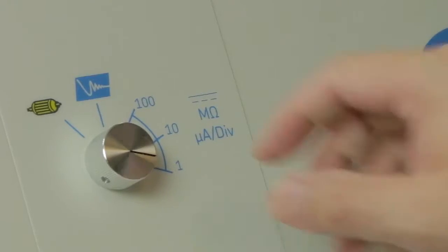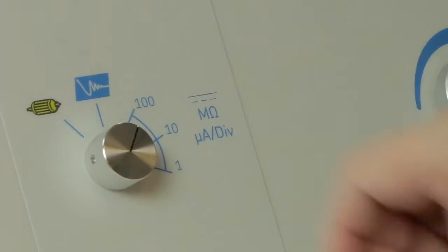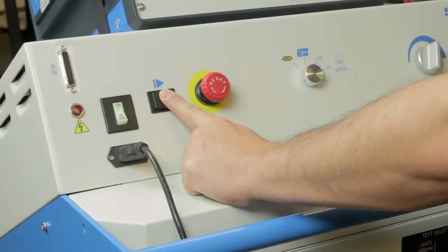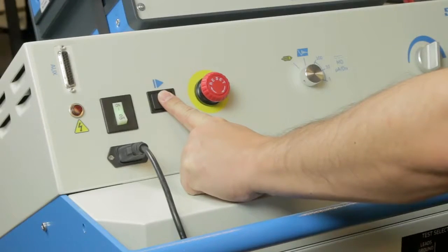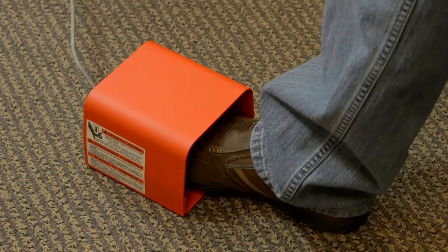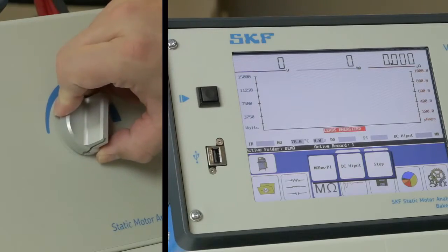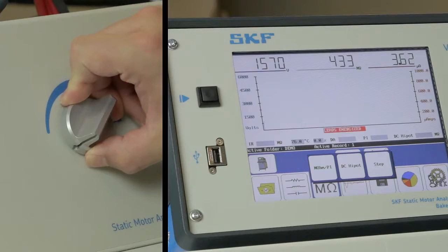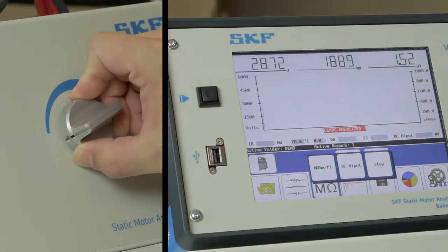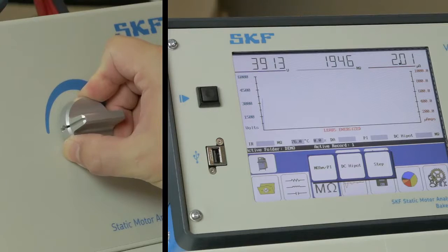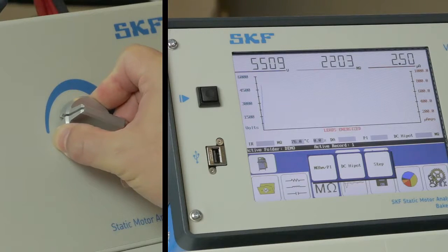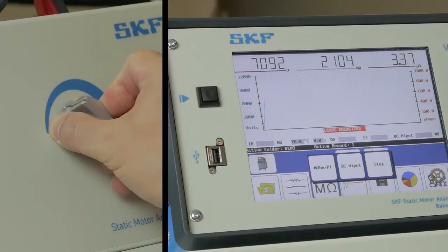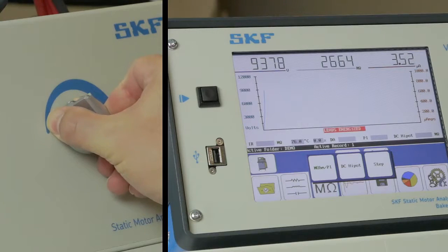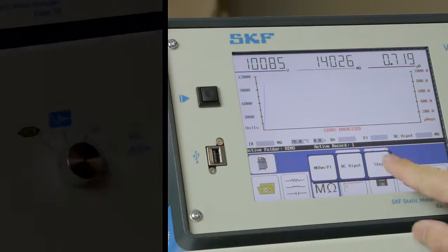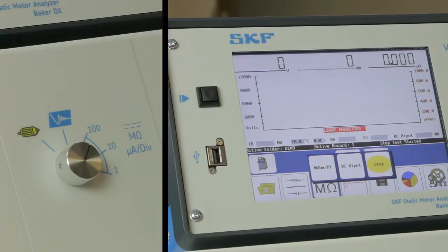Turn the power pack's function switch to the 100 microamps per division position. Press and hold the push to test button, or press and hold the foot switch if you have one. Smoothly turn the voltage control knob to raise the voltage to your first step. In this case, it's 10,000 volts. Press the step button to initiate the step timer, which by default will be 1 minute long.